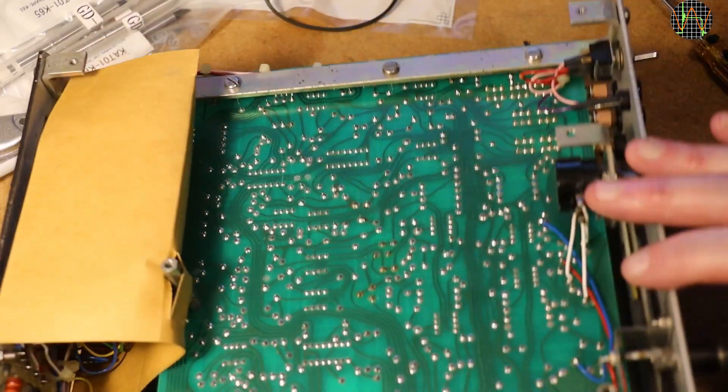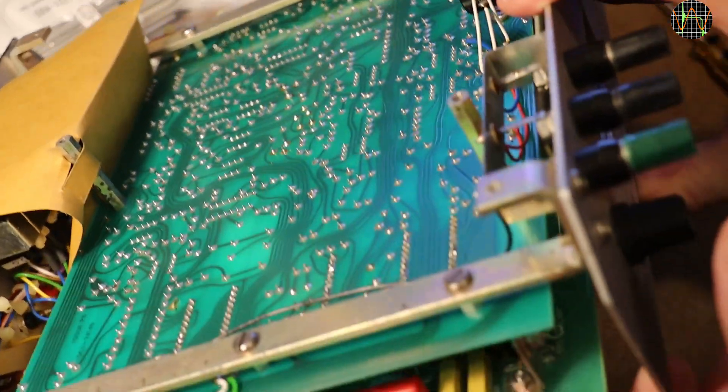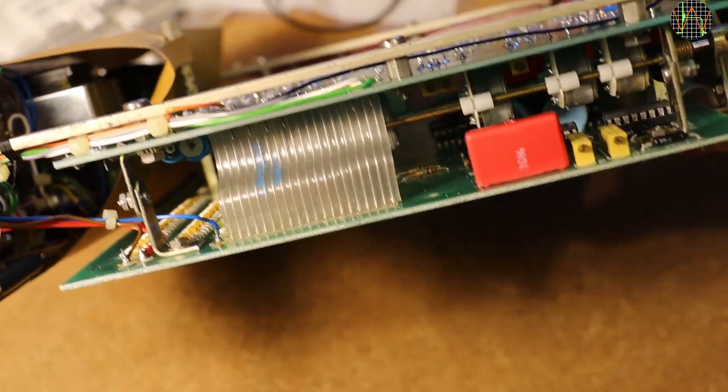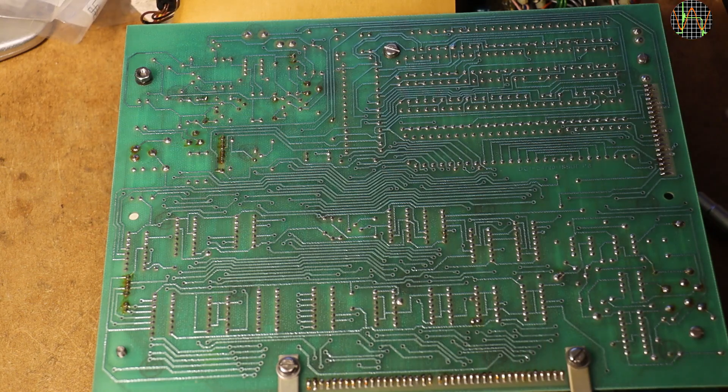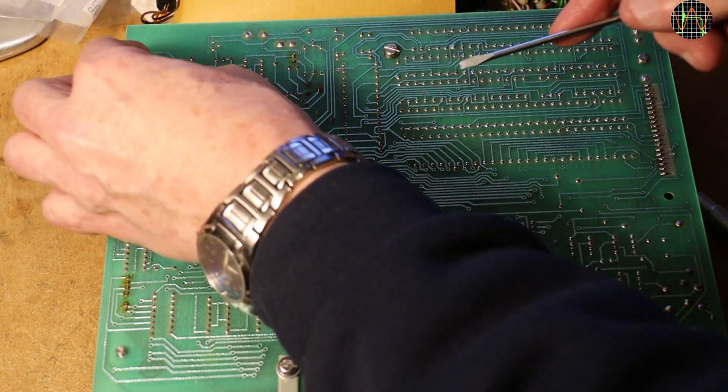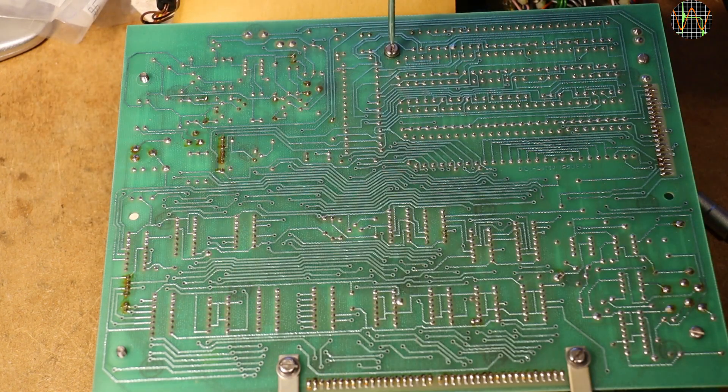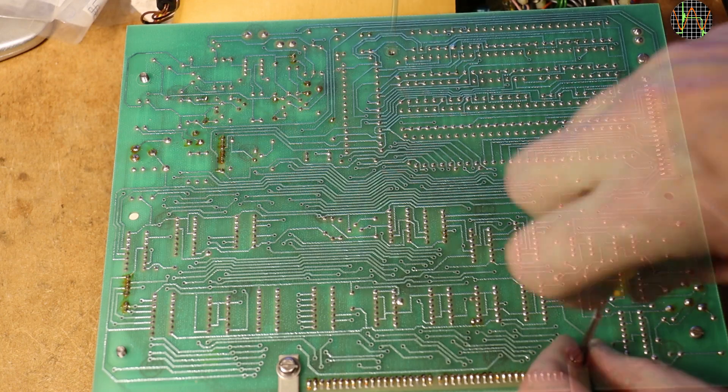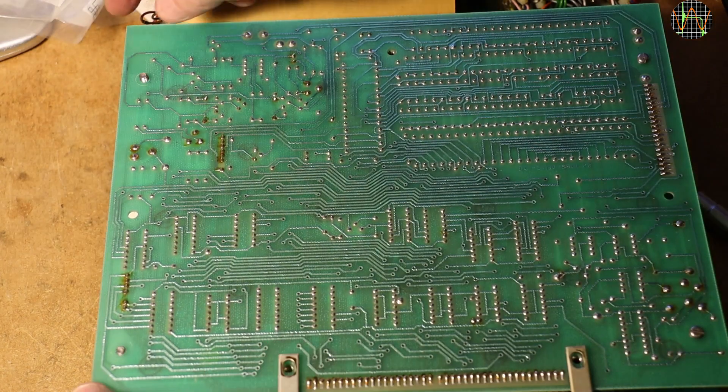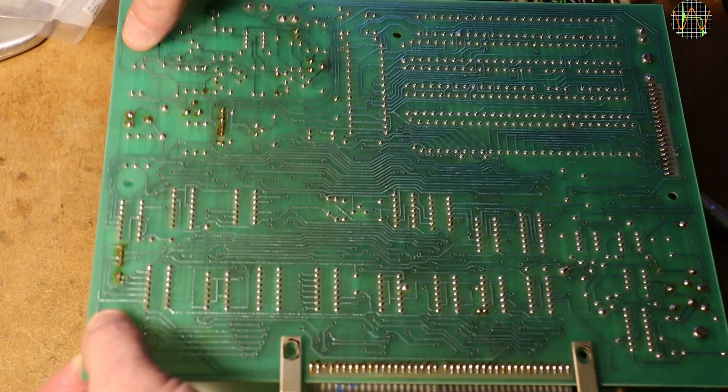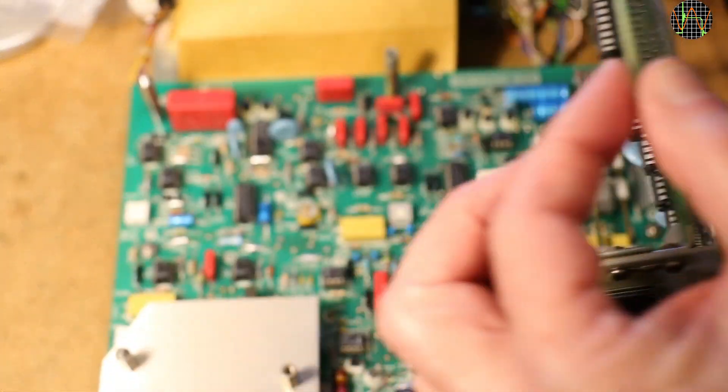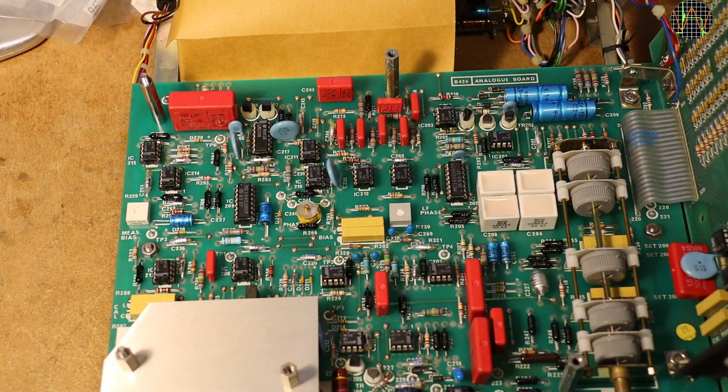The whole thing consists of a sandwich of 2 boards and some more circuitry at the rear panel. The top board can be lifted after removing the 2 nuts and an extra screw at the rear and 2 more screws that hold the display. The top board, which is the digital board, is on hinges and can be flipped open while still staying connected to the analog board below. The B424 stays fully functional in this mode which is nice.